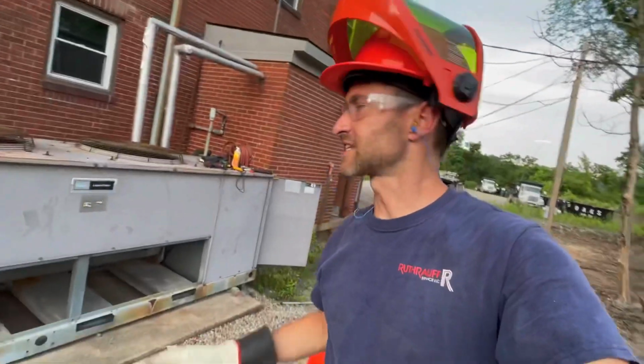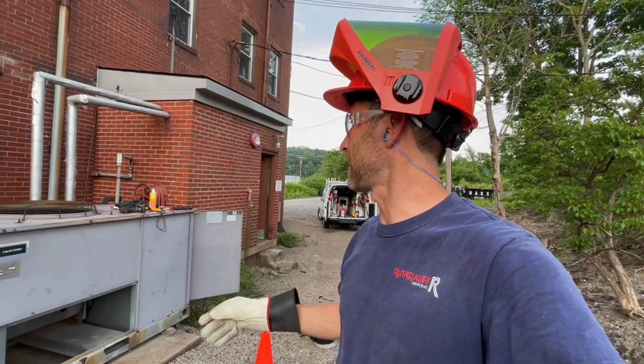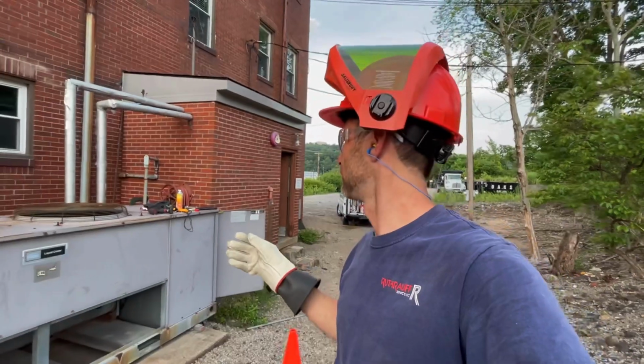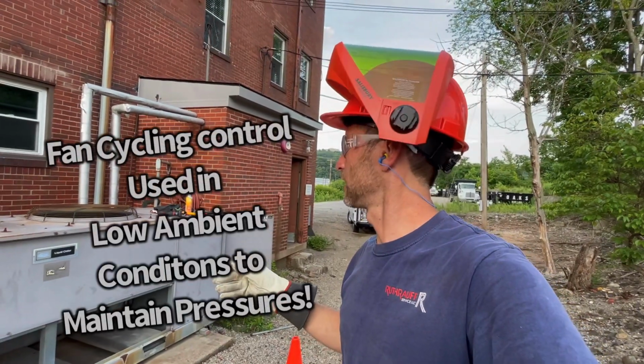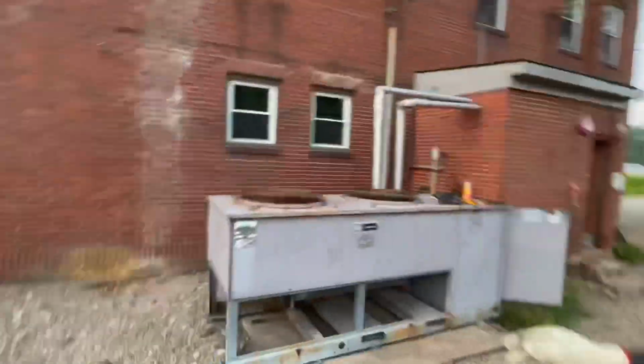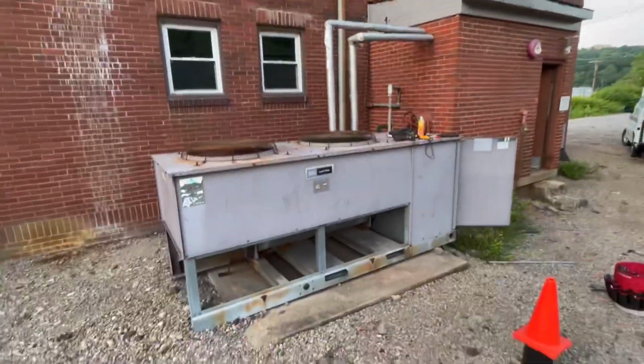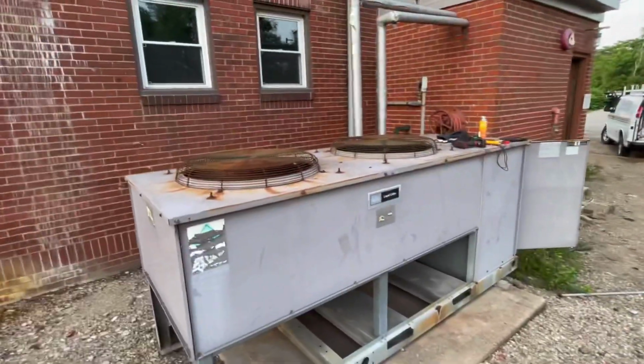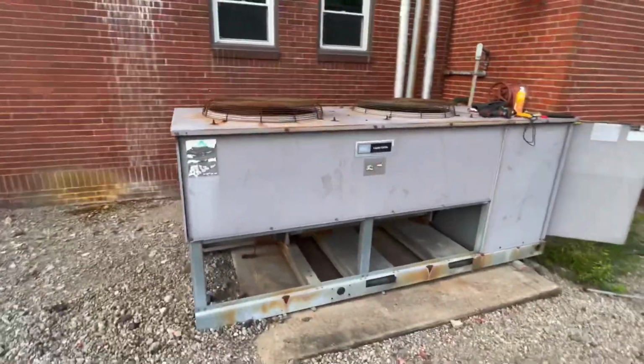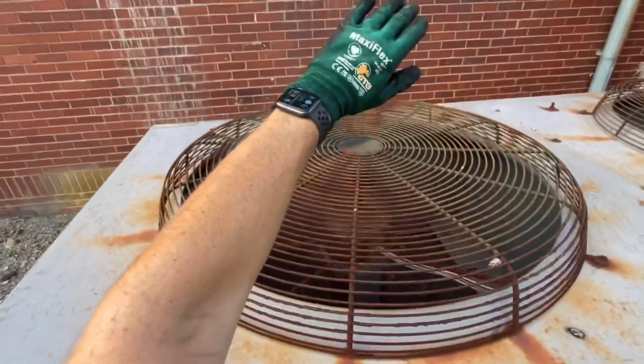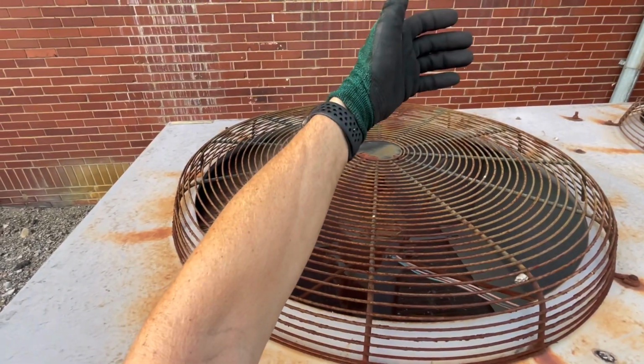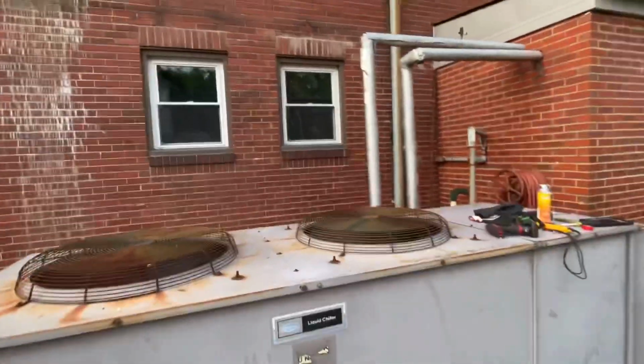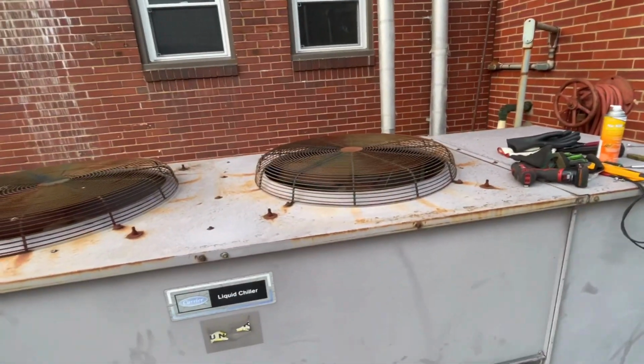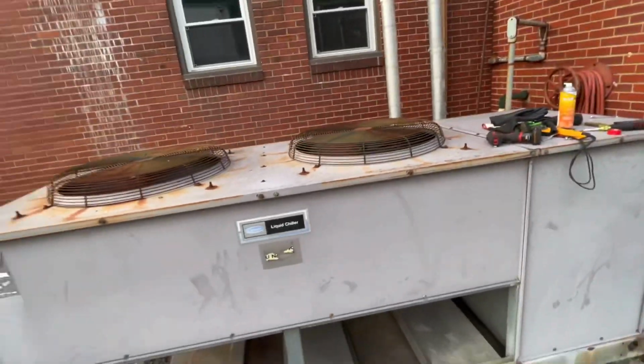On a hot day like this, if that second fan doesn't kick on, it's going to trip off on high head, unless we've got a bad fan cycling control. Let me wait and see what happens. If it doesn't kick on, I'm going to check out that fan and the fan cycling control if there is one. Getting pretty hot. Come on, baby, kick on. And we might have a bad fan motor. That might be the whole culprit.